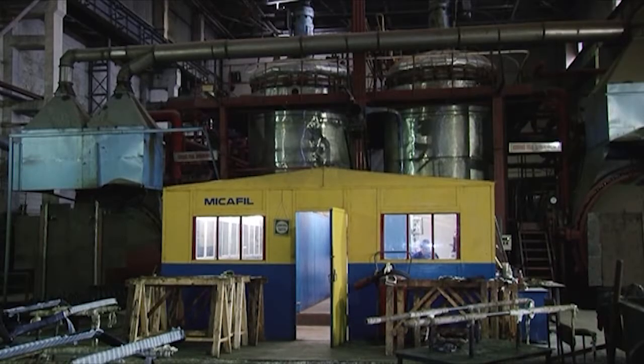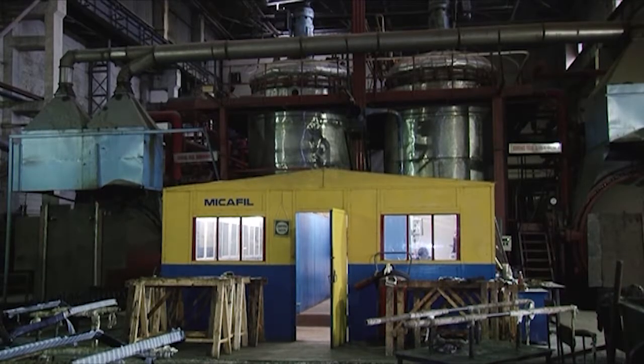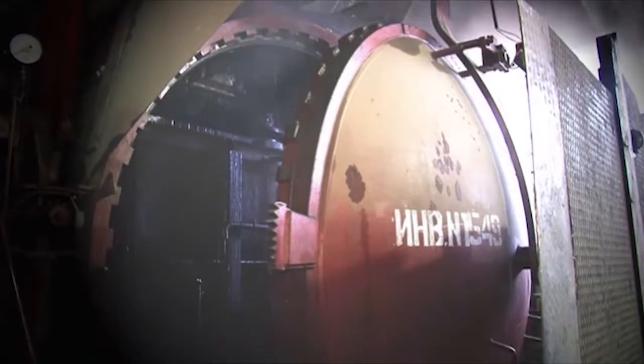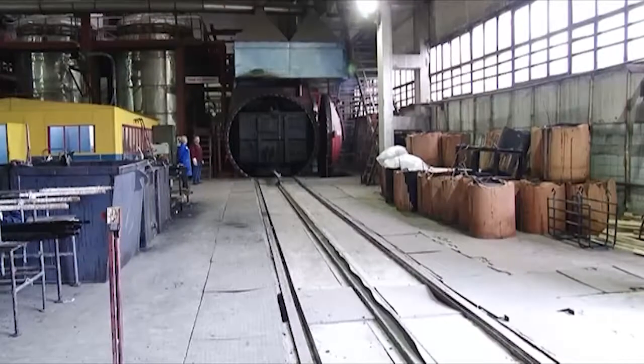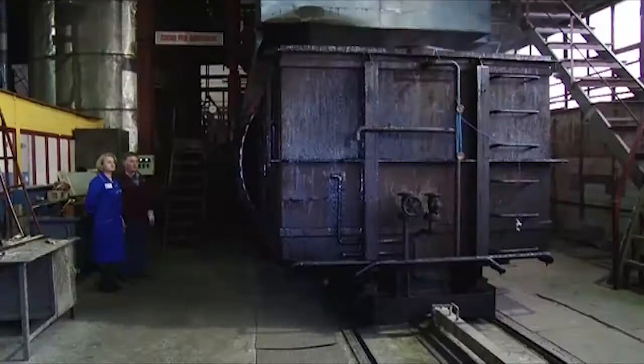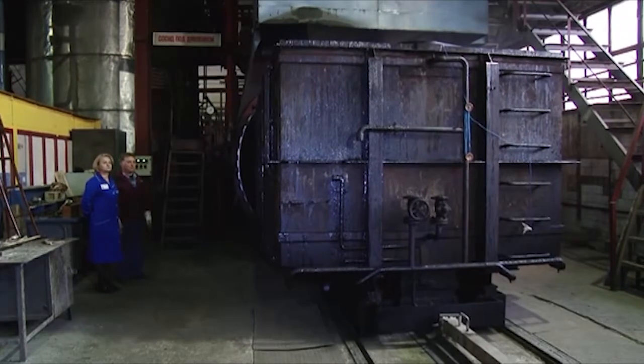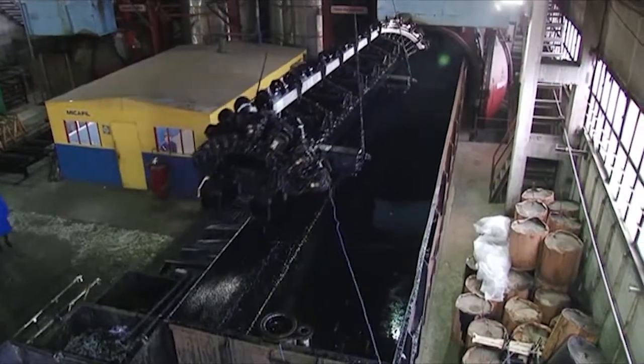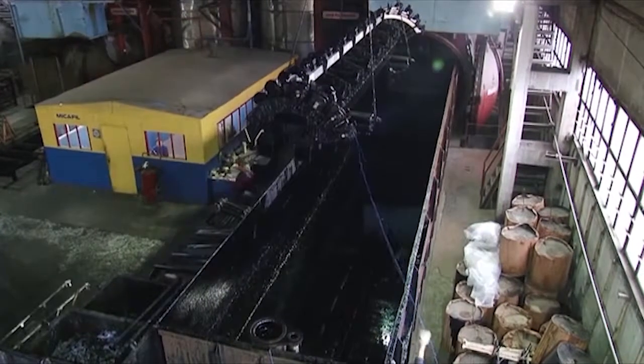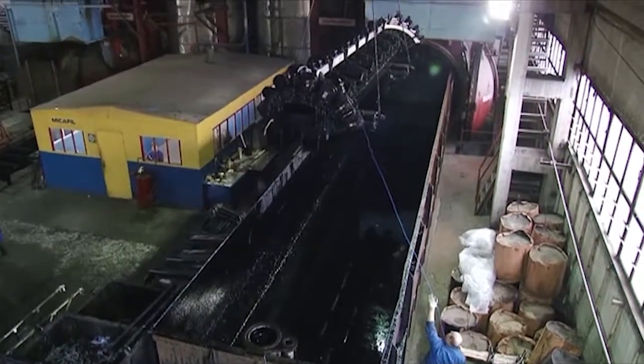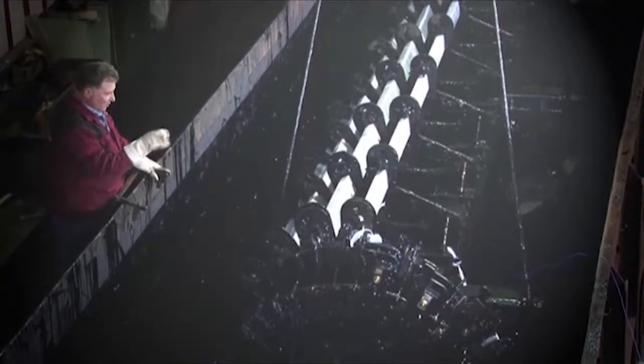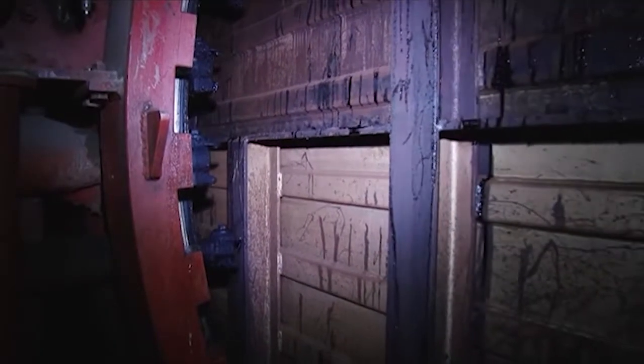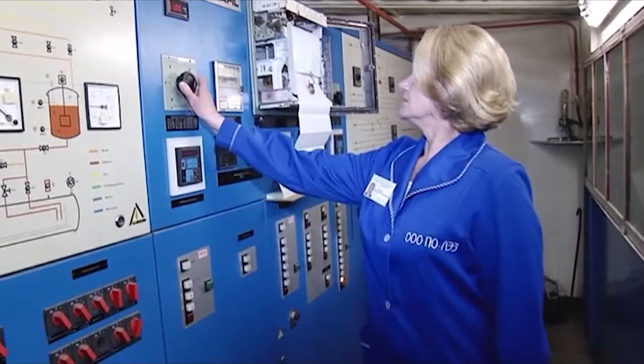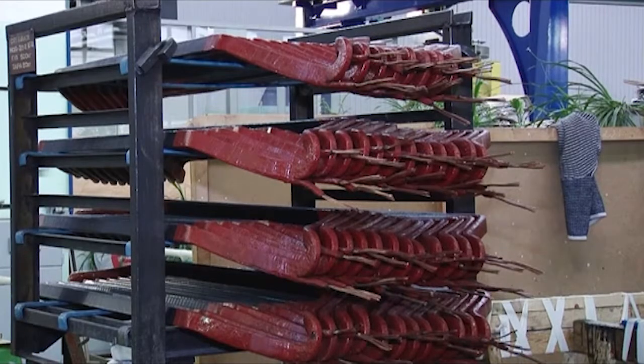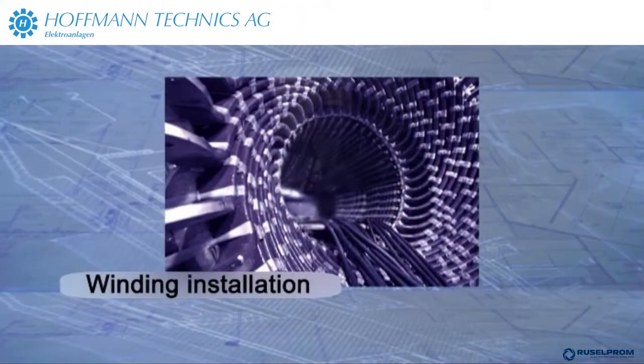The essence of the second method is as follows. Either bars or coils insulated with impregnated tapes are put into an empty bath. The bath is placed into a Micafil unit and the bars or coils are vacuumized. Heated bitumen is then fed from a mixing tank into the Micafil unit. Thus, the insulation is pressed and baked. The Micafil unit is highly productive equipment and allows the production of hundreds of coils and dozens of bars in a shift, providing for the pressing of not only slot section insulation, but also of end winding insulation, thus making it possible to carry out high voltage tests for both sections of the coil. Such technologies result in coils of the highest quality.